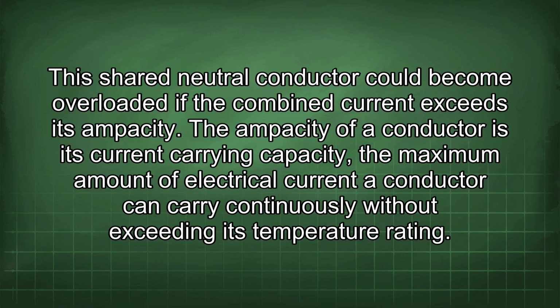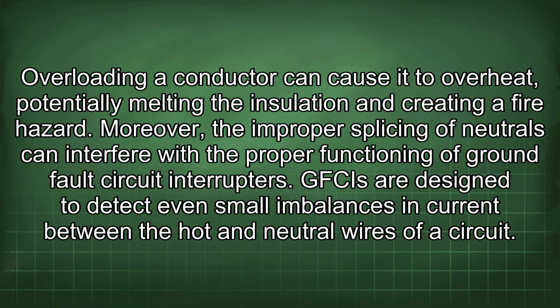This shared neutral conductor could become overloaded if the combined current exceeds its ampacity. The ampacity of a conductor is its current carrying capacity, the maximum amount of electrical current a conductor can carry continuously without exceeding its temperature rating. Overloading a conductor can cause it to overheat, potentially melting the insulation and creating a fire hazard.